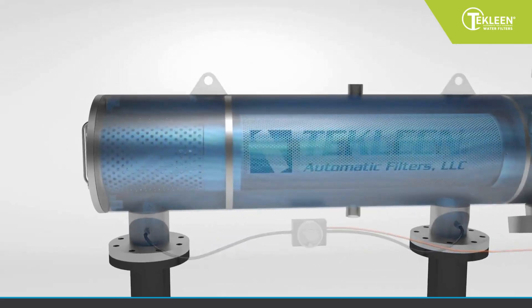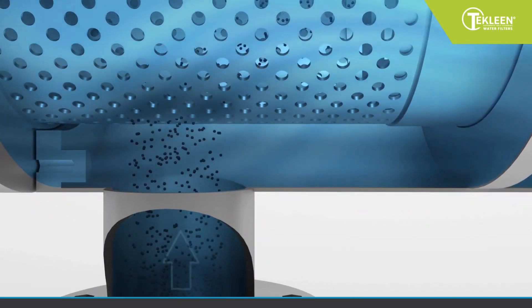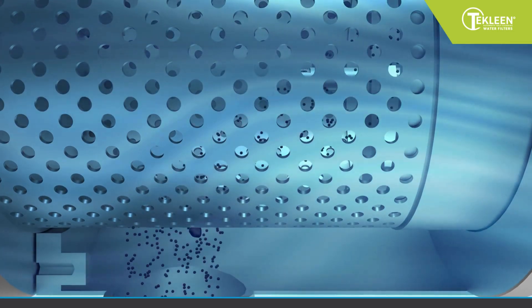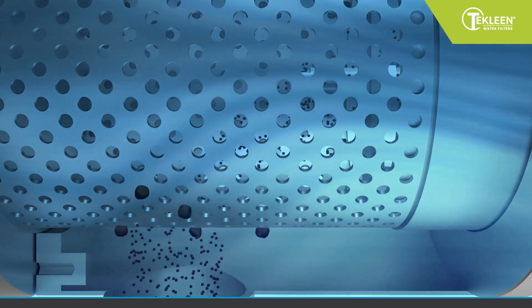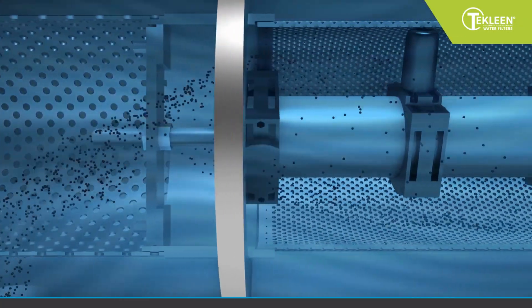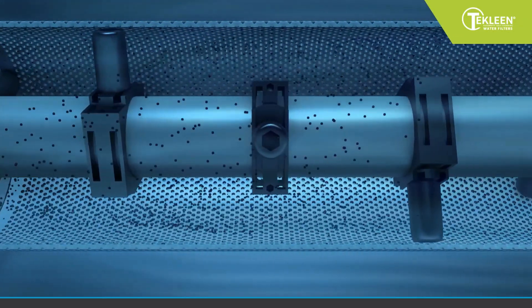Let's take a closer look at how our filters operate. Dirty water enters the filter through the inlet and passes through a coarse screen that protects the fine screen from any large particles that might damage it. The water then moves down the center of the filter body, passing through the fine screen.